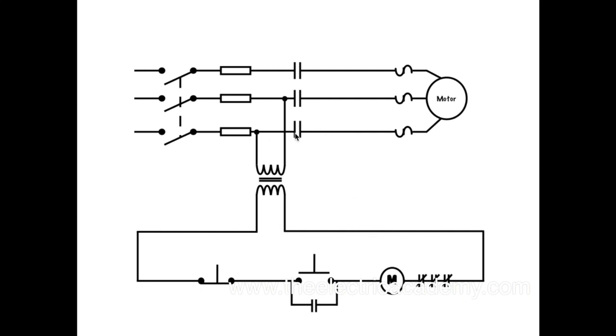Now I talked about how these are connected. These overload heaters here are actually like a bimetallic strip or a solder pot. They're physically attached to these overload contacts down here. So if the heaters open up - if these trip - then it's going to open up these normally closed contacts in the control circuit and the whole circuit shuts down.